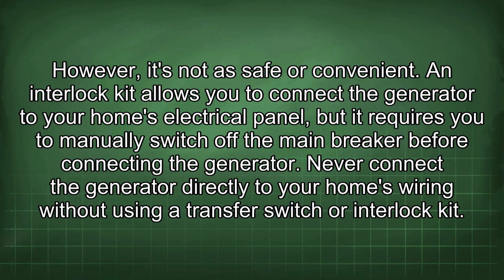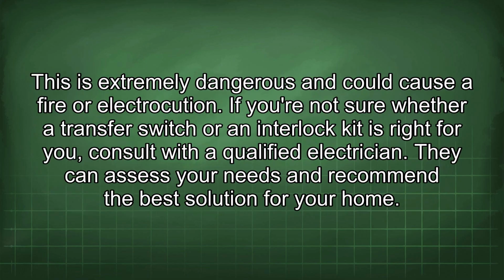An interlock kit allows you to connect the generator to your home's electrical panel, but it requires you to manually switch off the main breaker before connecting the generator. Never connect the generator directly to your home's wiring without using a transfer switch or interlock kit. This is extremely dangerous and could cause a fire or electrocution. If you're not sure whether a transfer switch or an interlock kit is right for you, consult with a qualified electrician. They can assess your needs and recommend the best solution for your home.